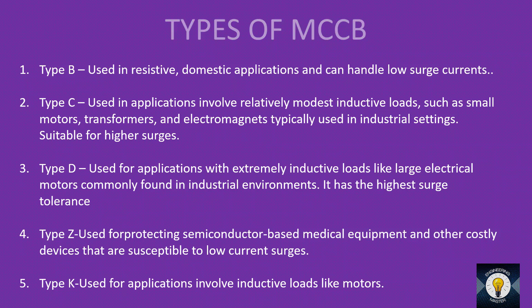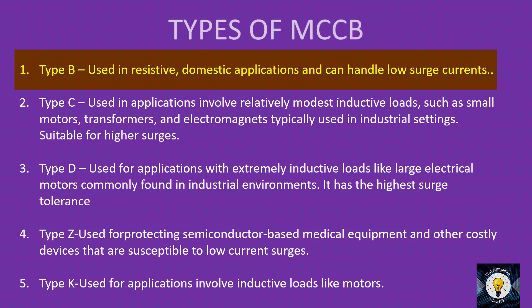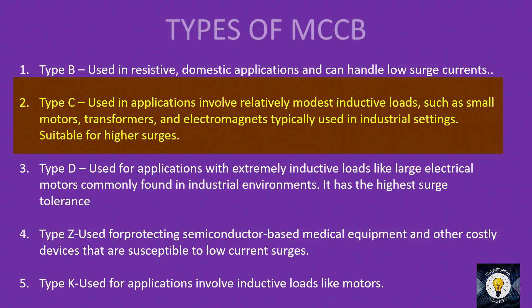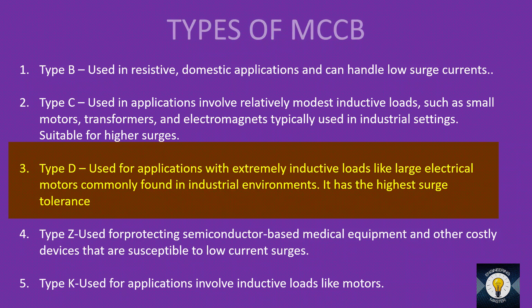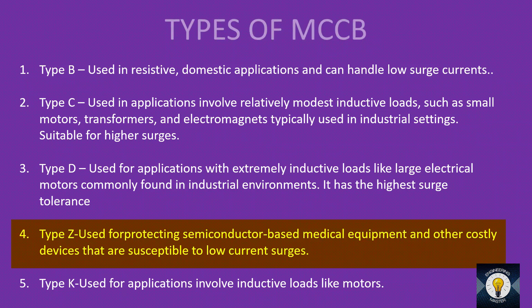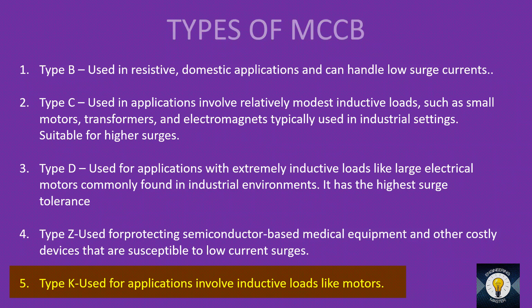Type B MCCB is used in resistive or domestic applications and can handle only low surge currents. Type C is used in commercial applications involving modest inductive loads such as small motors, transformers, and electromagnets. Type D has the most surge tolerance, used for relatively high inductive loads like large electrical motors — more of an industrial type. Type Z is used to protect delicate semiconductor-based equipment as it has the lowest surge tolerance and trips between 2 to 3 times full load current. Type K is used for the protection of inductive loads such as motors.